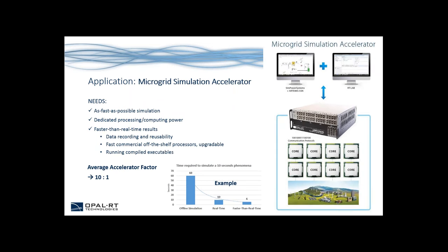The fourth application is the microgrid simulation accelerator — faster-than-real-time simulation — requiring dedicated processing power. The goal is faster-than-real-time results with data recording using fast commercial off-the-shelf products that are easily upgradable. Based on our experience, we can achieve an average acceleration factor of 10 to 1. For example, a 10-second phenomenon that takes 60 seconds offline and 10 seconds in real-time could be achieved in 6 seconds in faster-than-real-time.